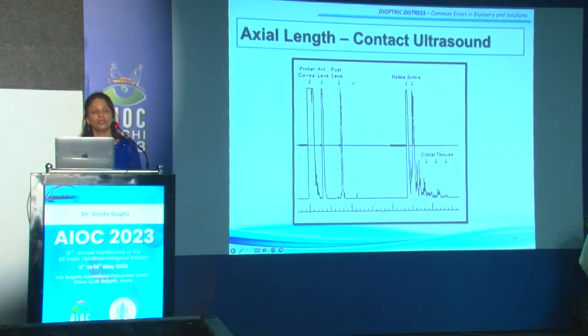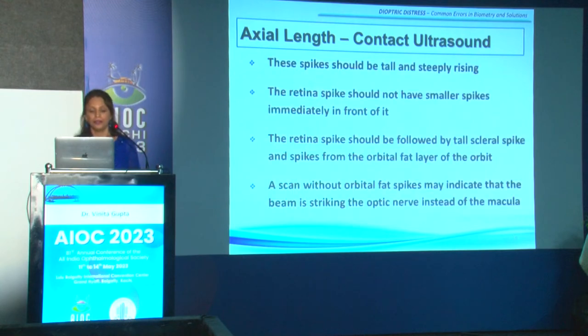So as I was talking about the spikes, ensure that each spike is tall and steeply rising from your baseline. The retinal spike is almost of the same reflectivity as your lens and the posterior and the scleral spikes, and there should not be any small spikes immediately in front of the retinal spike. There should be a tall scleral spike immediately after your retinal spike, with the attenuating orbital fat spikes. If these attenuating orbital fat spikes are not there, it indicates that your probe is going through the optic nerve and not through the fovea. Remember that. So these orbital attenuating fat spikes are also very important in your scan.